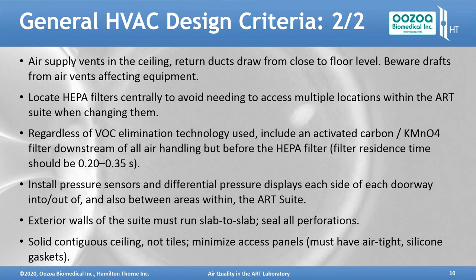Regardless of the VOC elimination technology that you use, you need to include an activated carbon and permanganate filter downstream of all air handling but before the HEPA filter. And the residence time on this filter should be about 0.2 to 0.35 seconds. So even if you're using PCO or plasma technology, you'll still need some other filters, because stuff can still get through those and you need to be just sure that you're controlling those.